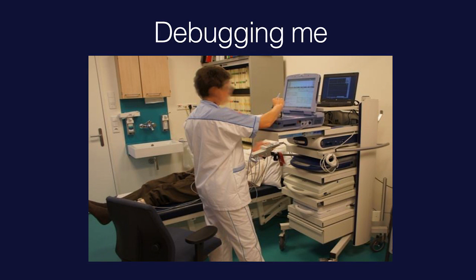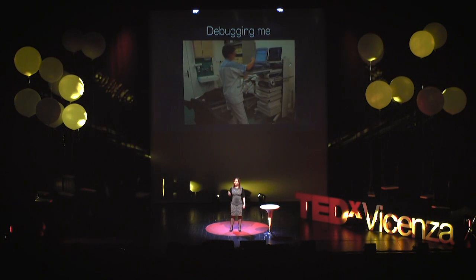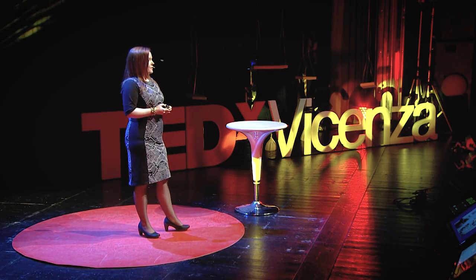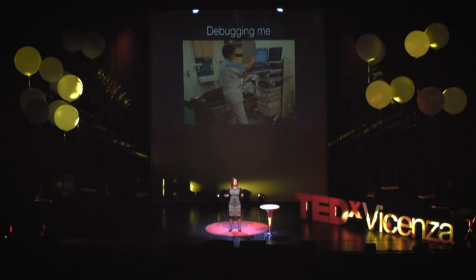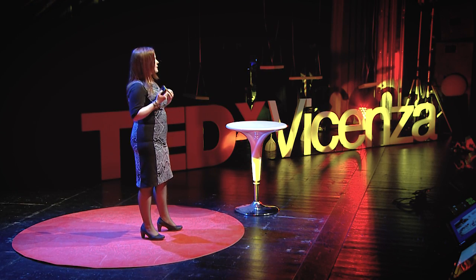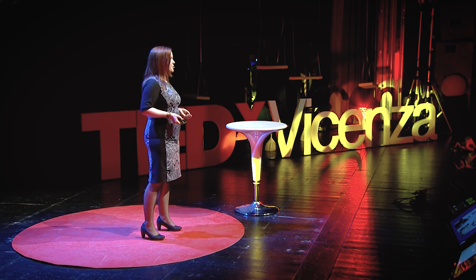After returning from this trip, I went to a checkup at the hospital to see if they could figure out what was wrong. This is what it looks like when the pacemaker technician is controlling my heart with the touch of a pen to the touch screen at the pacemaker programmer. There's a stack of different programmers from different vendors because they all communicate in different non-standard ways with the implants. On this screen, there are buttons for making my heart go faster, making my heart go slower, and even turning off the pacing completely. The problem was that the number shown on the programmer screen indicating the upper heart rate limit was not the same as the actual settings of the pacemaker. Because of this software bug, it took several months before they could figure out the problem, and in the meantime I would get the same feeling of sudden exhaustion whenever I was trying to run for the bus or walk up some long stairs.